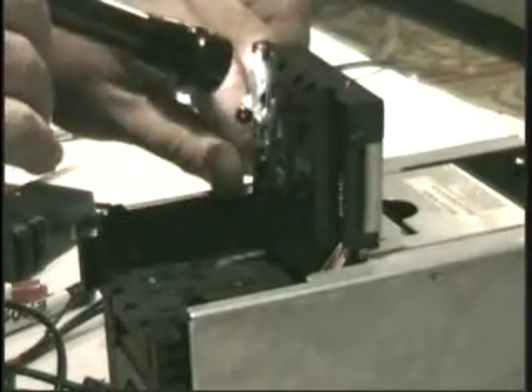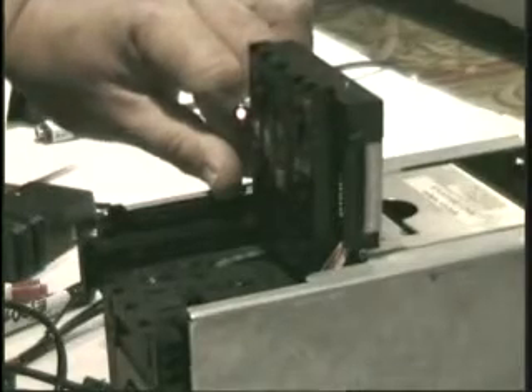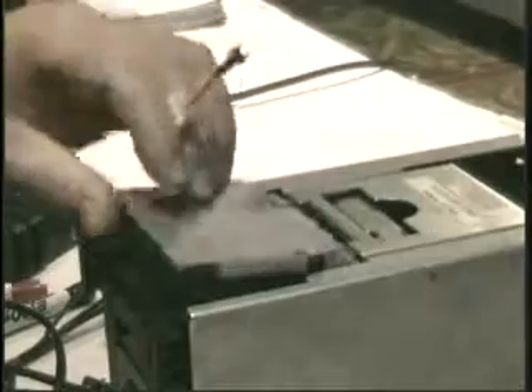If you can turn that test light off with a flashlight, you know the photo sensor in the upper board's working—it's got to be the LED that's burned out if it stays on when it's closed, so you change the lower board. If you can't turn it off with a flashlight, then you know it's the upper board; the photo sensor's not working. Just a quick test to tell you which board has failed if you ever get one that doesn't work.